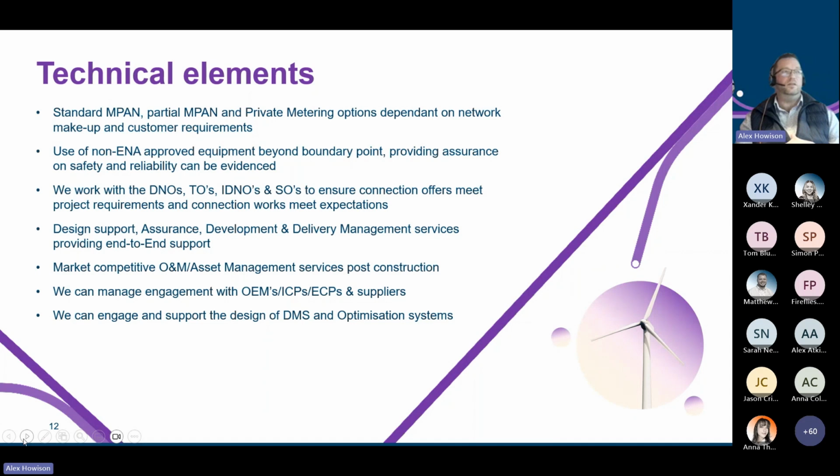that if there's a need to have full settlement, we're adhering to BSC, so the Elexon metering codes will all apply. And I think having compliant metering, whether that's COP 1 to 10 metering, depending on your connection type and the customer type, even in an environment where you've got private sub metering for different connections downstream, avoids some of the longer term risk when you want to change supplier, or if a customer wants to change supplier. It means they're not having to look at meter changes further on down the line, although that is obviously a preference that can be mapped out in the early part of the project.